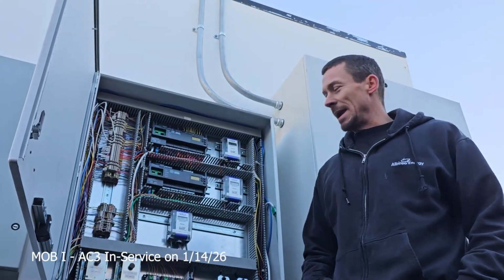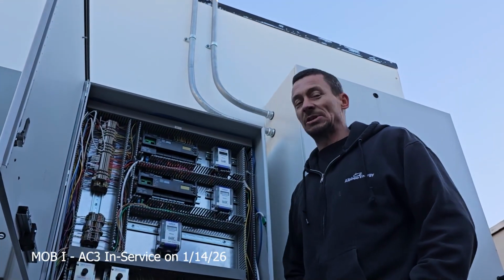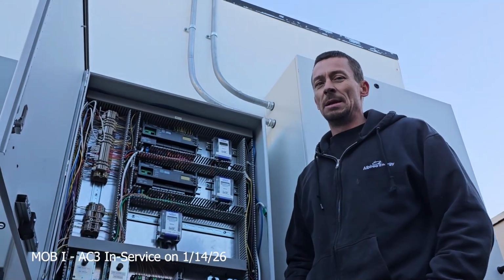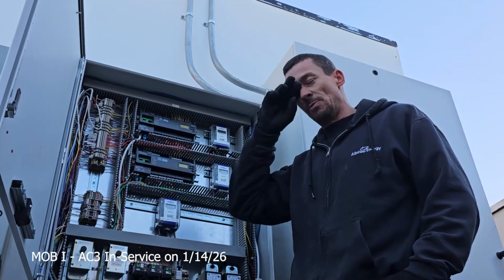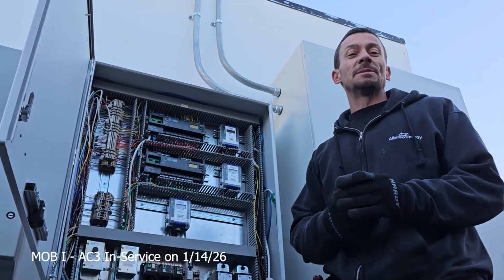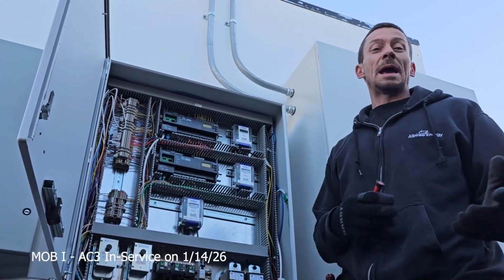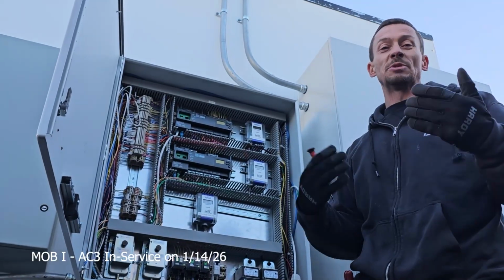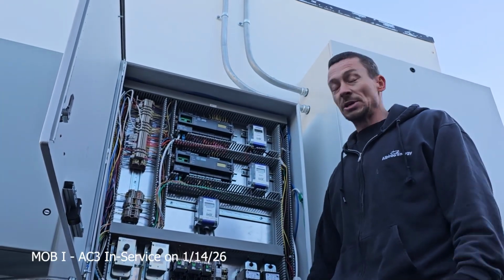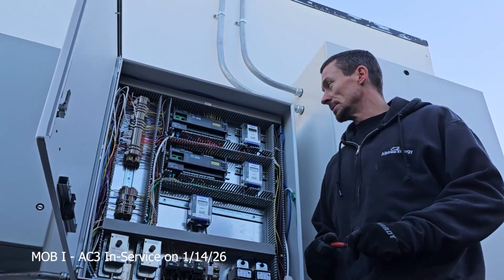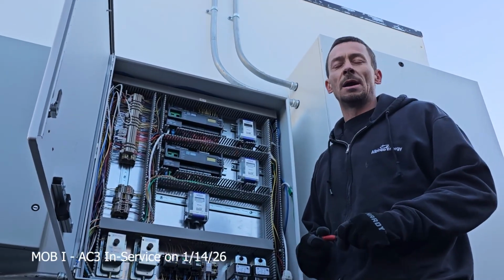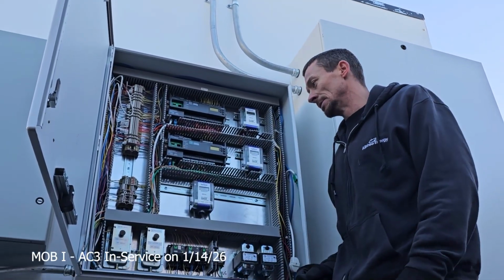Cool. But I don't think that's it. If you have a comm issue, it's not like MSTP, it's a little different. Sometimes it gets on a different baud rate, or something happens where the controller needs to be restarted. Typically you can try, but I haven't. Usually for BACnet, you don't see that, at least I don't.